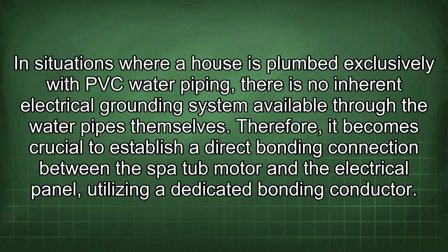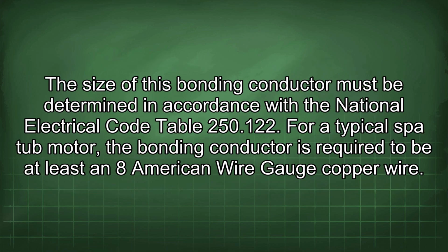In situations where a house is plumbed exclusively with PVC water piping, there is no inherent electrical grounding system available through the water pipes themselves. Therefore, it becomes crucial to establish a direct bonding connection between the spa tub motor and the electrical panel, utilizing a dedicated bonding conductor.